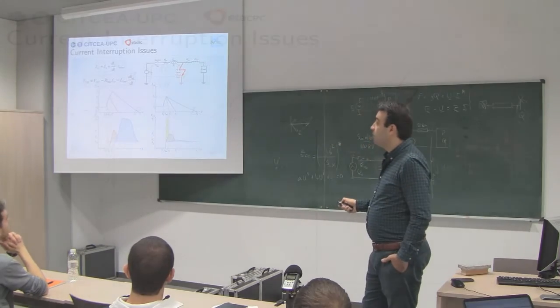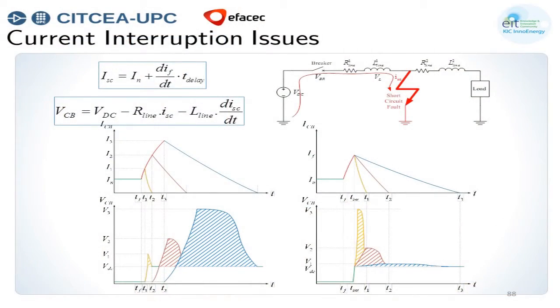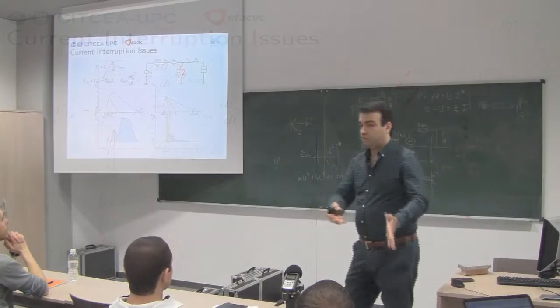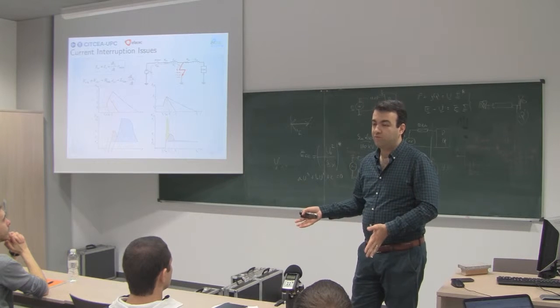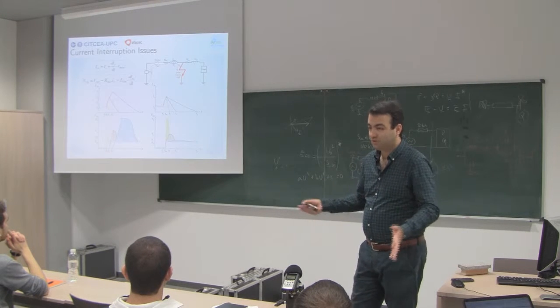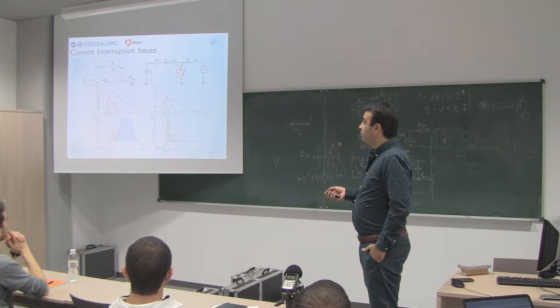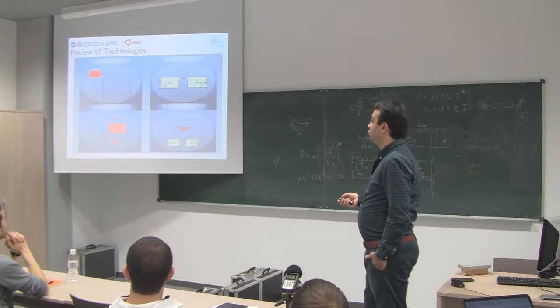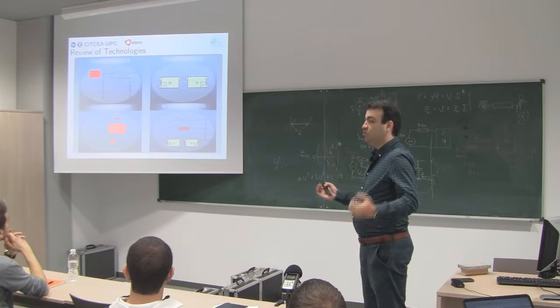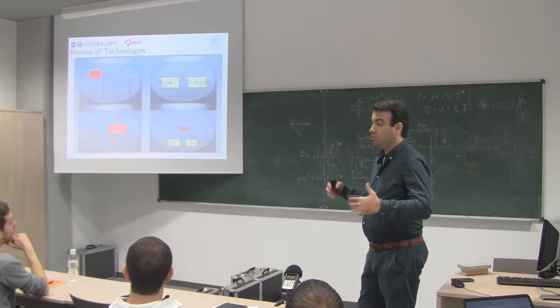So you will have this term positive, and it will add up to this VDC. So you will have a high voltage, high transient voltage across your breaking device. So if you're supposed to design your device for 320 kV, it might be exposed to 1000 kV during the switching, and it will be destroyed.